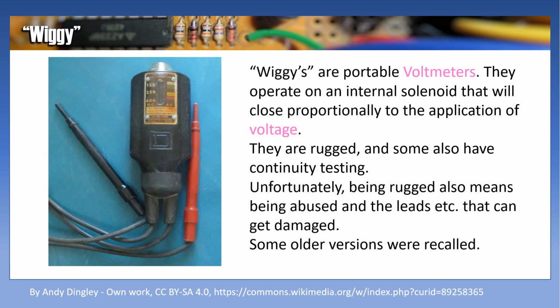Another device that you may see or run into in your trade is something called a wiggy. Wiggies are portable voltmeters. They operate on an internal solenoid that will close proportionally to the application of voltage. They are rugged, and some have continuity testing as well. Unfortunately, being rugged also means being abused, and the leads, etc., can get damaged. Some older versions were recalled, so be aware.